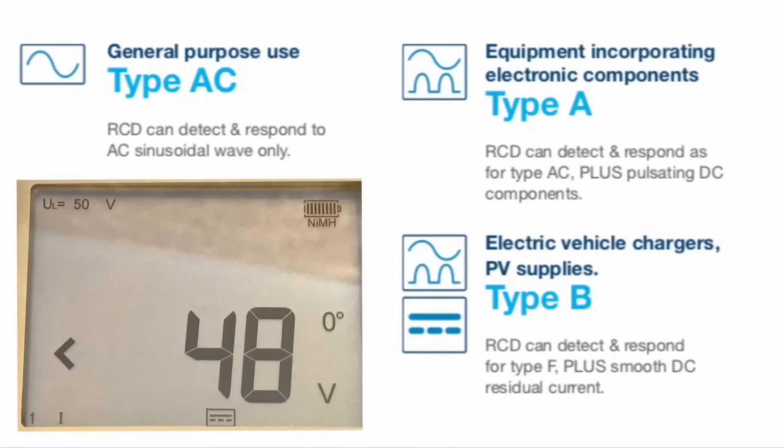Lee has just shown us how to set the Megger MFT tester up to test for B-type RCDs. What sort of protection do they offer? They're going to protect us against all the loads that a type AC would protect us against and all the loads that a type A would protect us against, and then they move forward onto things like solar PV, electrical vehicle charging where the smooth DC fault current is greater than 6 milliamps. These B-type RCDs are almost like the Rolls-Royce of RCDs. And as always, we need to be checking the manufacturer's instructions to see exactly what their recommendations are for the type of RCD to be used.